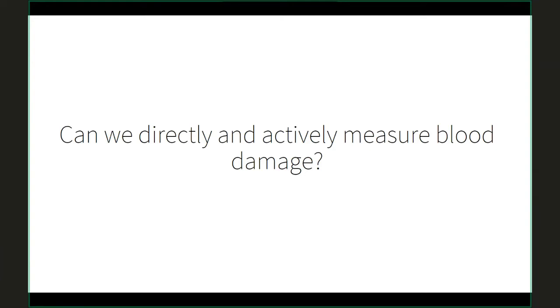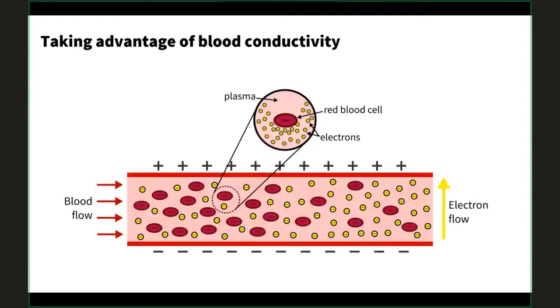We asked: can we directly and actively measure blood damage? Thinking mechanically, we wanted to take advantage of blood conductivity. Red blood cells float in plasma, which is electrically conductive — it passes electrical charge. The more blood cells present, the harder it is for electrons to flow through the plasma, because blood cells are electrically insulating. However, as cells break open they release hemoglobin, which is rich in iron and is conductive. So as more blood cells break, the overall conductivity of the blood increases — it becomes less resistant to electrical charge.